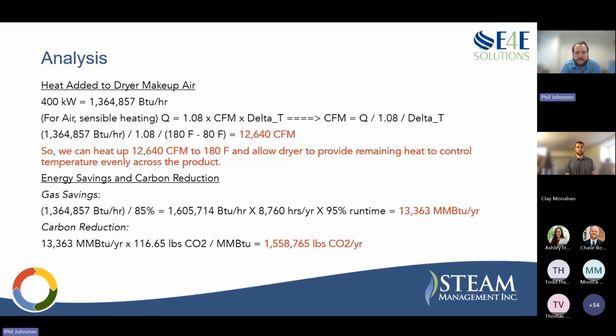Going through a similar calculation on the savings, if we assume that burner's 85% combustion efficiency running pretty much all the time, if the plant's a 24/7 operation, that comes out to 13,000 MMBTU per year, which would be pretty significant savings, and over 1.5 million pounds of CO2 per year. So pretty good emissions reduction as well.